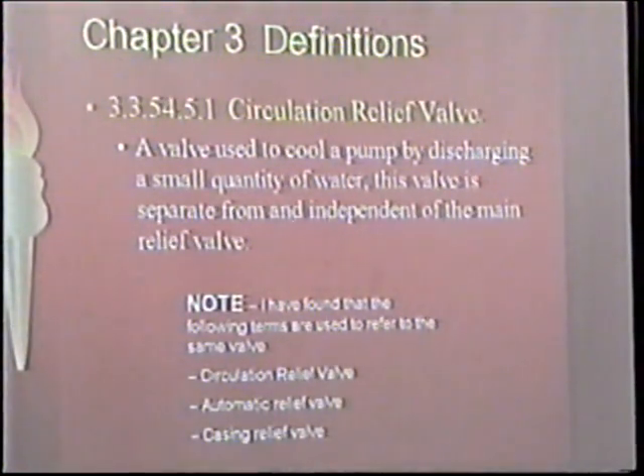They also define what a circulation relief valve is. We call it a casing relief valve or circulation relief valve. It's a little 3/4 inch valve typically that's on a fire pump that discharges enough water to keep the pump from overheating when there's no flow in the system. It's also called, later on in part of 20, an automatic relief valve. And I sent a note off to NFPA. I said, what's that? And they said, yeah, you're right, it's used interchangeably.